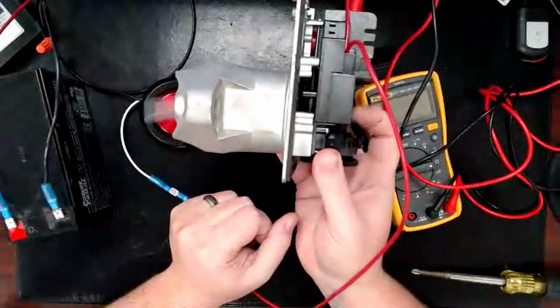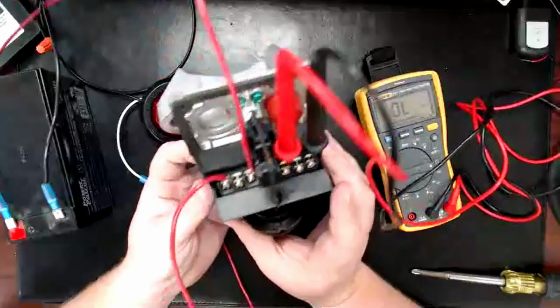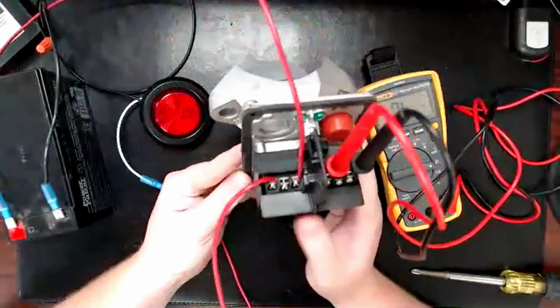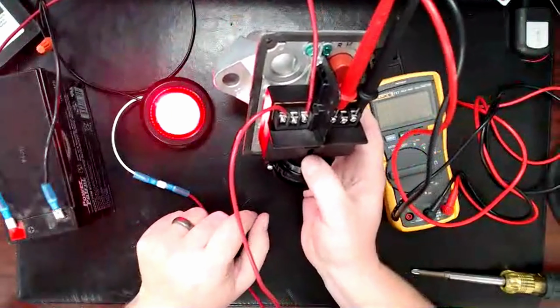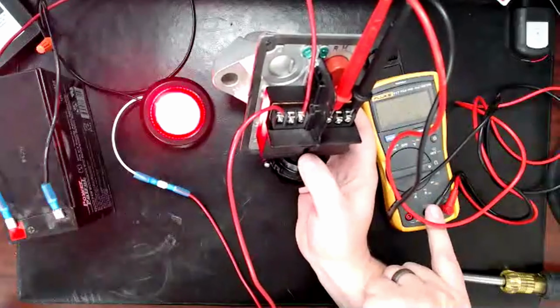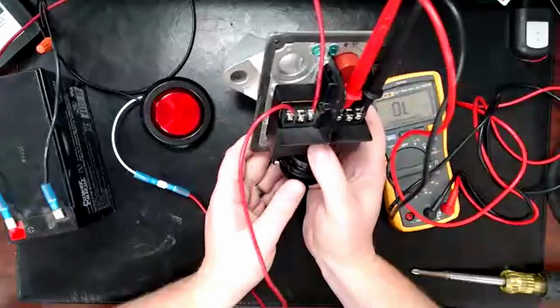Also, when this is in the pipe, you obviously can't grab this side of the circuit and move it. This little part right here, if I move that, it's directly attached to that paddle. So that's a way you can test it if you're trying to make it switch states real quick. But you saw every time I pulled on that, it turns on this LED light. So that would be ringing the bell. And you also see over here, we're going in and out of our alarm state at the same time. The meter's a little slower than the light. The light's a better status indicator. But that's, in simple, the way that you hook it up.